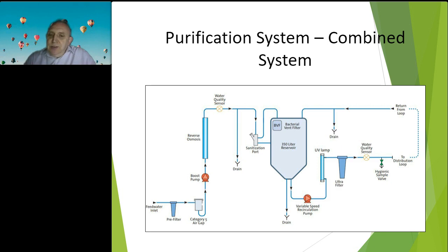Why do we think the ring main is important? Why are we circulating the water, okay? You look at the ring main, we have a UV lamp. We have another filter, okay? Along that ring main, you're going to have connections for washer disinfectors and any other equipment you may have connected.